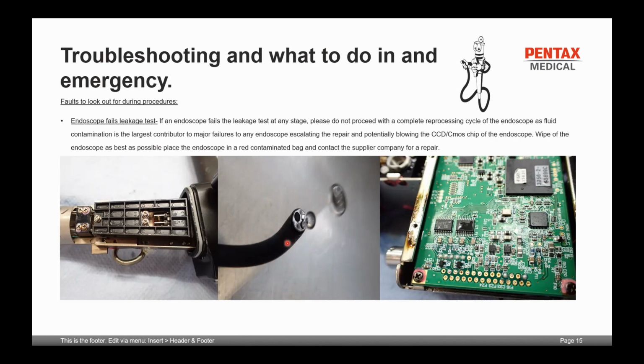Patients come in for a gastroscopy. Some patients have bad back teeth, or a chipped molar. A bite block prevents the patient from biting down on the endoscope, but doesn't prevent broken teeth. And if the patient struggles during the intubation period and it nicks the bending rubber and perforates any part of it, your CCD and CMOS chip is positioned right there at the distal end of the endoscope. And if it goes undetected, a leakage test doesn't get completed, the endoscope goes through a reprocessing cycle, and you fluid contaminate your endoscope.